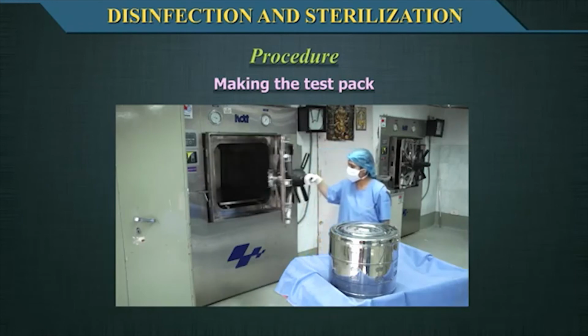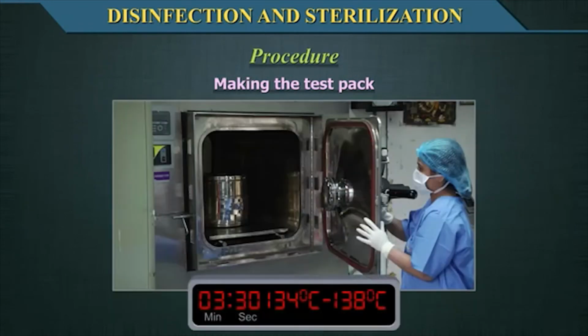It must be subjected to a standard sterilizing cycle. The holding or sterilizing time should not be more than 3.5 minutes at a temperature of 134 degrees Celsius to 138 degrees Celsius. Reading the test.